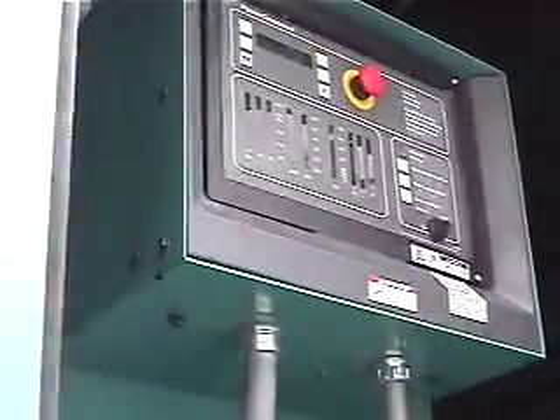Goes all the way up. Transfers the air out. Up inside this panel is where the LAN's tied into for the generator. So if you undo those two screws right there on the right side, that swings open to the left and you can see our LAN wires in there. So all these devices are showing up on the LAN chart then? Yeah, so that generator screen I showed you on the graphics, that's where all those points are coming from. That's from the connection here. So if you need to troubleshoot where the connection is, that's where to come to, right here.